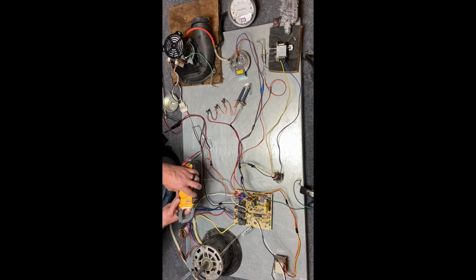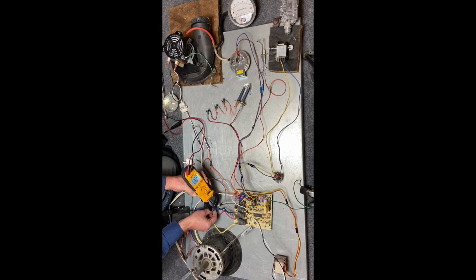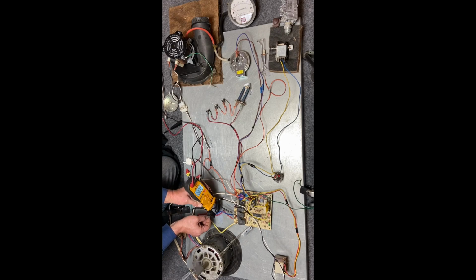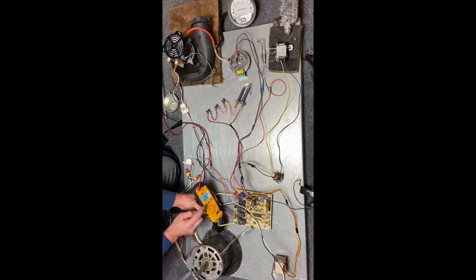Now if I wanted to see what speed is really being used, I can also check my high speed, 0 amps. I check my medium low or heating speed, 0 amps. And if I check the side for fan or circulate, I end up with 1.5 amps. So we know that's the speed being used, and my unused speed, 0 amps, so it's also not being used.